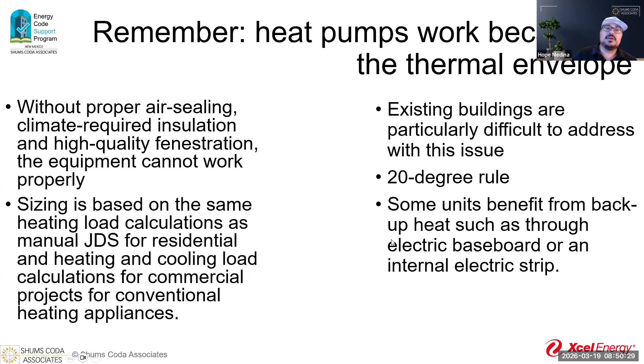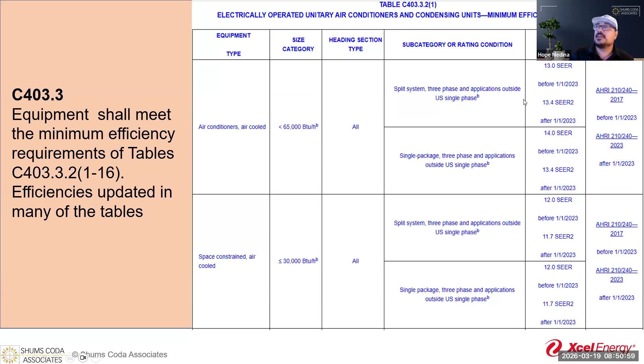To regulate this, we go to C403.3, where we see the minimum efficiency tables. Looking through these, SEER regulates things like air conditioners—basically anything doing cooling—and it also regulates heat pumps. Same with HSPF. These are where we evaluate whether a system is as efficient as it needs to be.